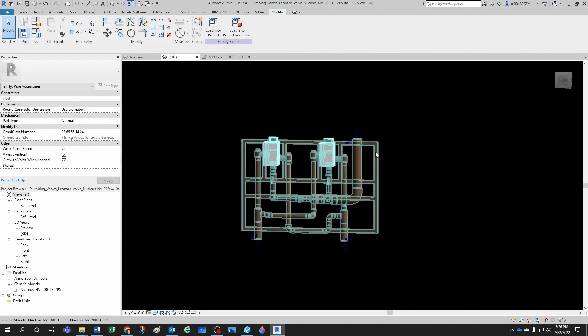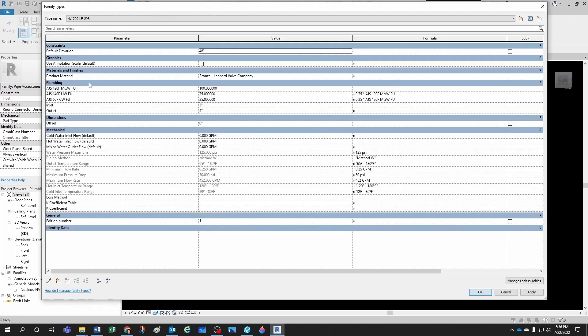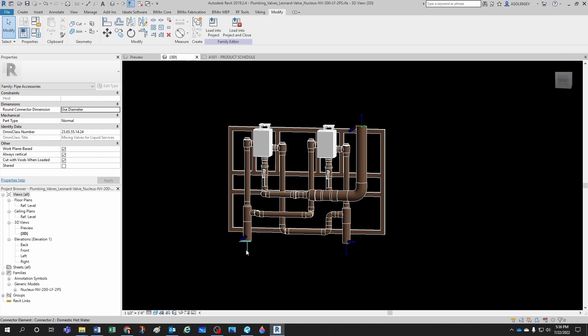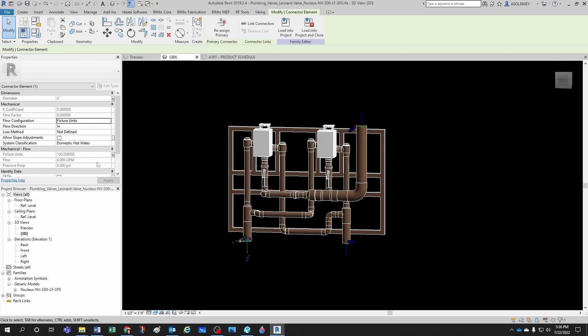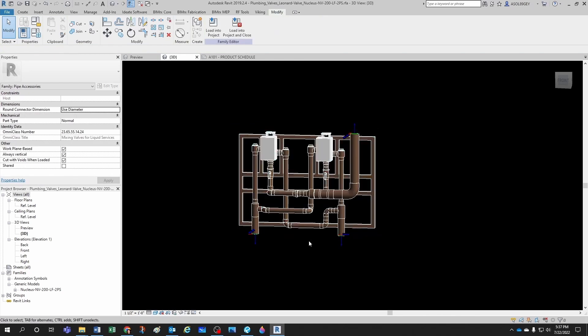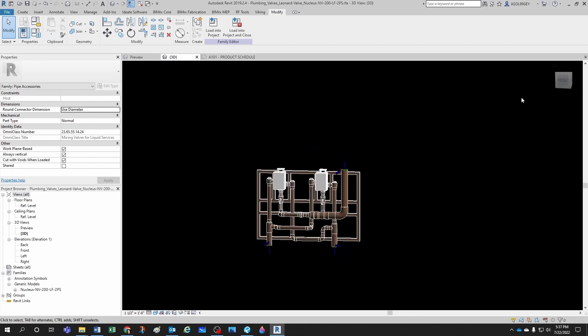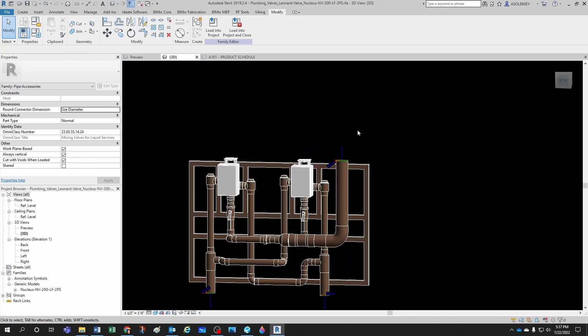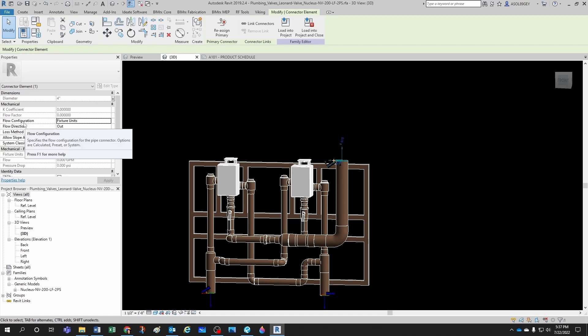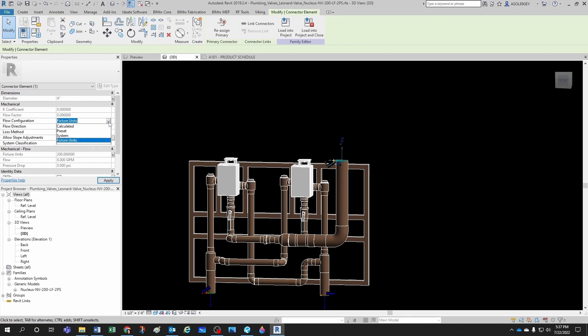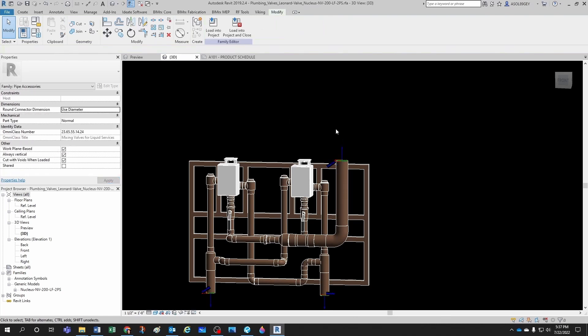Let's verify everything is working. I change the mixed water fixture unit parameter to 200 — it works. Set it to 150 — works. Set it to 50 and now the hot water reads 37.5 and cold reads 12.5. Now for the outlet, instead of a fixed fixture unit value, I change it to 'Calculated' so it reads the value out of the connected system automatically. Let's test that.